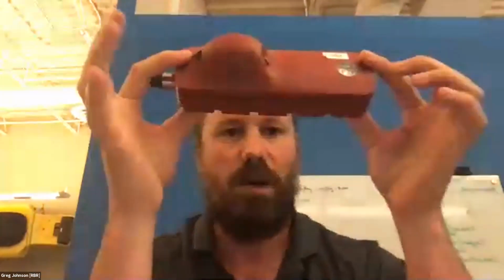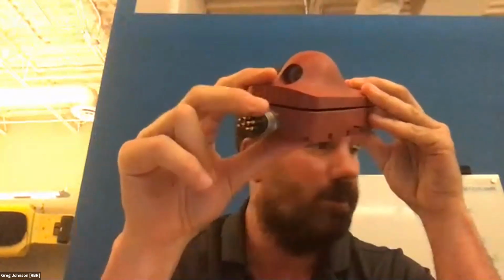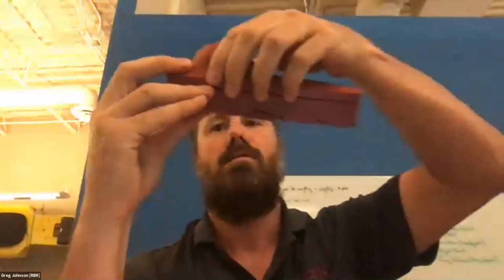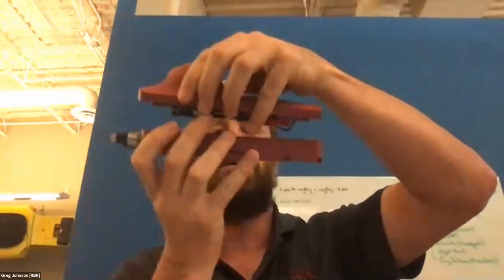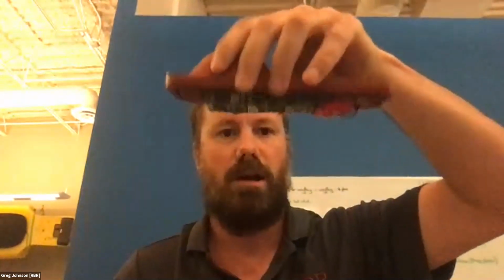The K factor is particularly helpful if you have a mixed fleet of, let's say, some Slocum and some Sea Glider, and you want to switch the CTD between the two. You just need to set the K factor and off you go. We have two versions of the Legato. This is the wet bay version, which has an MCBH on the back end. And then we have the dry bay version, which looks a bit like that, where it's electronics underneath, and you don't need the bottom shell at all.